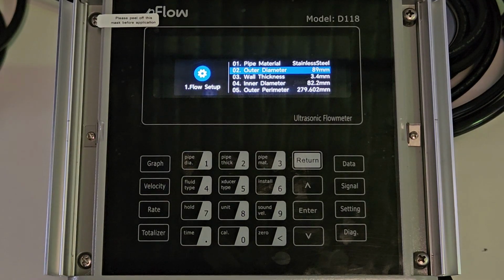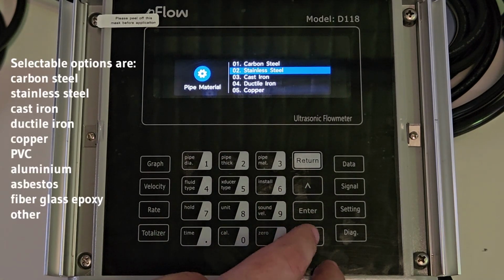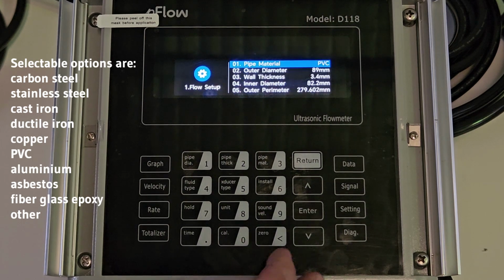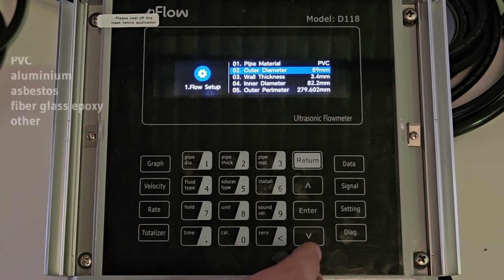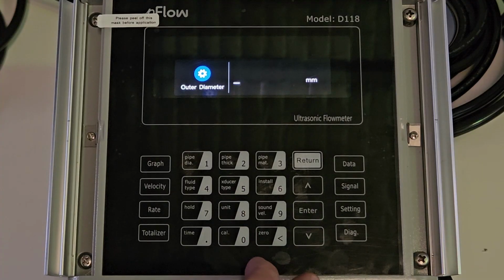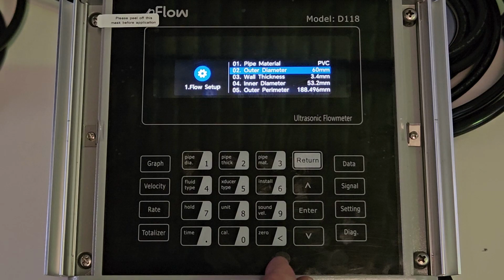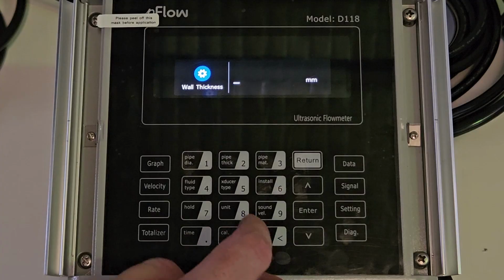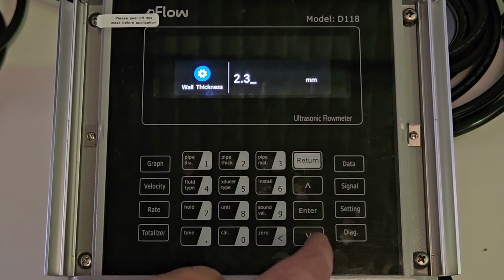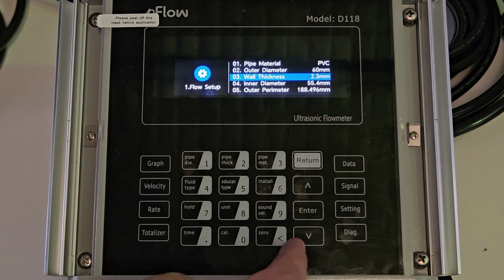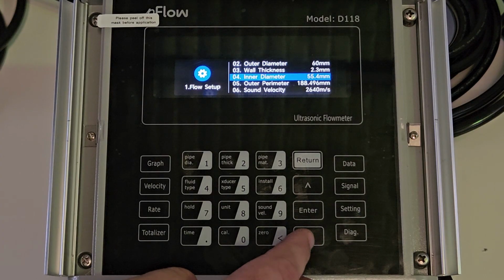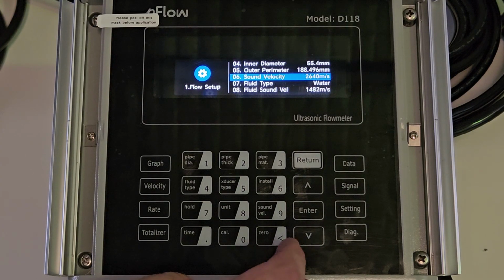First press the pipe diameter shortcut button. From here press up to highlight pipe material. Press enter and you can scroll a list of selectable materials. I have selected PVC. Next press down, then enter again. Now enter the pipe outer diameter, which I have entered 60 mm, then enter. Then press down to highlight wall thickness. Press enter, then type the pipe thickness, 2.3 mm in this case. Then enter to confirm. Inner diameter and outer perimeter will calculate themselves if you enter those 2 figures.